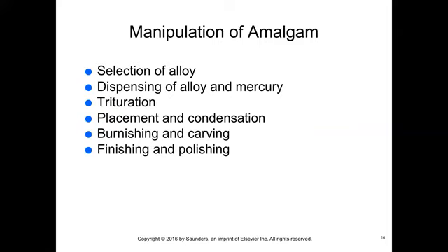Powder and mercury are mixed together in a mechanical device called a triturator or amalgamator. Each manufacturer of amalgam materials provides specific time and speed specifications regarding the mixing of a particular material. Under-triturated amalgam appears dry and crumbly and sets too quickly. Over-triturated amalgam appears wet and sets quickly, producing heat. Properly triturated amalgam has a satin-like appearance.